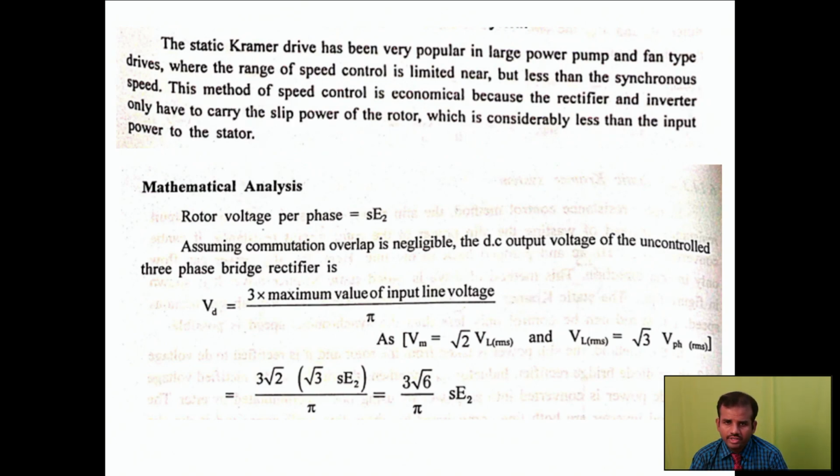This static Kramer drive has been very popular in large power pump and fan type drives because the range of speed control is limited to nearly but less than the synchronous speed. This method of speed control is economical because the rectifier and the inverter only have to carry the slip power of the rotor, which is considerably less than the input power to the stator.